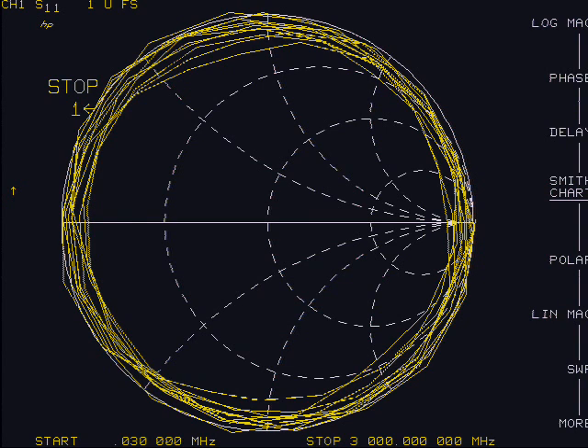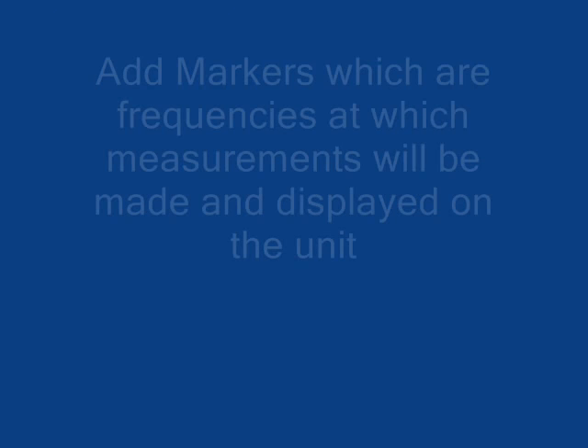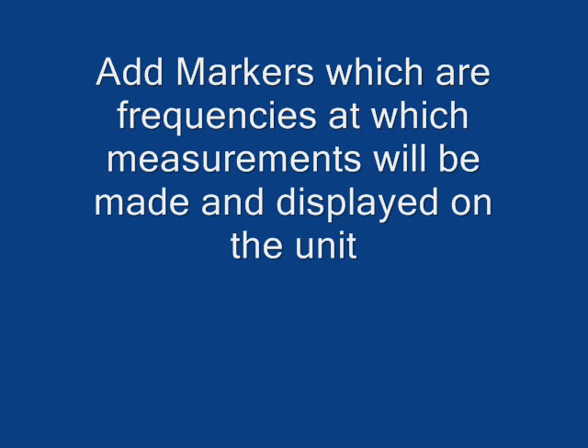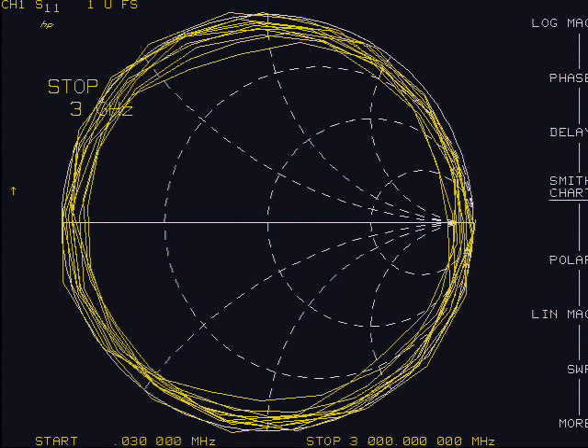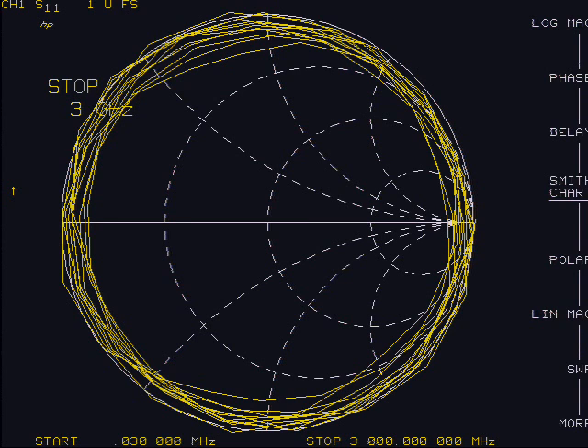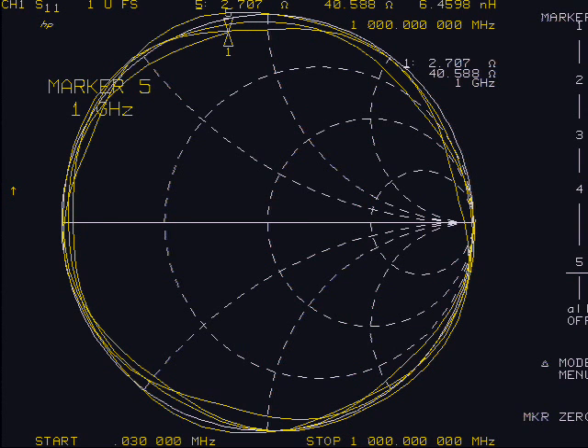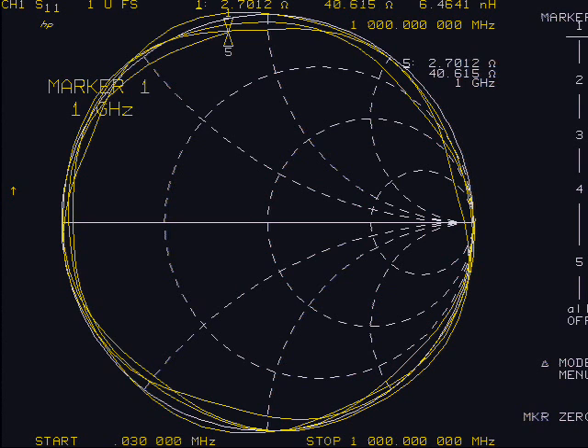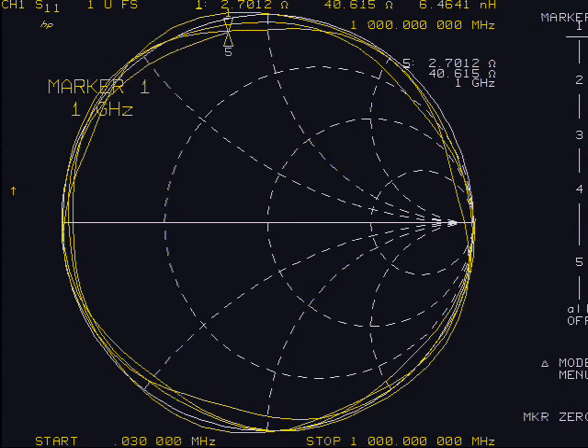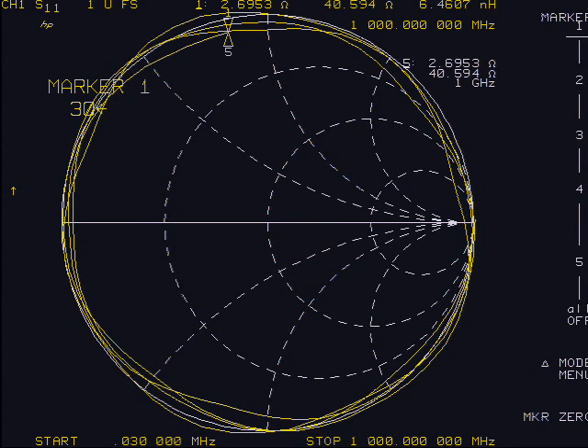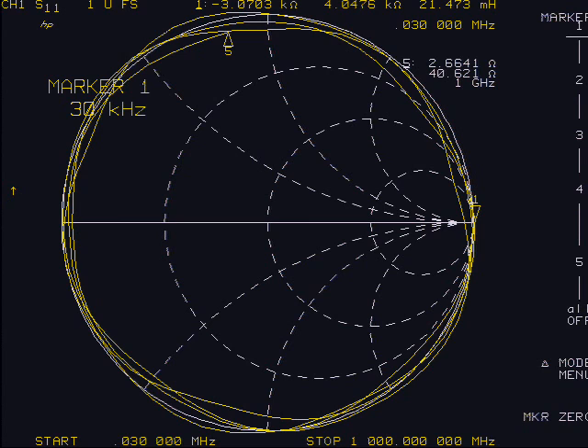Set frequency markers, which are measurement points for the high and low frequencies being used. Select the marker button. Markers default to the highest frequency or the stop frequency, then the number 5 soft key. Set the number 1 marker to the starting or low frequency, which defaults to 30 kilohertz, by selecting the number 1 soft key, then keypad 3 0 K slash M.